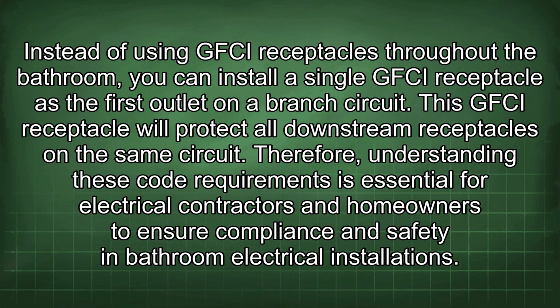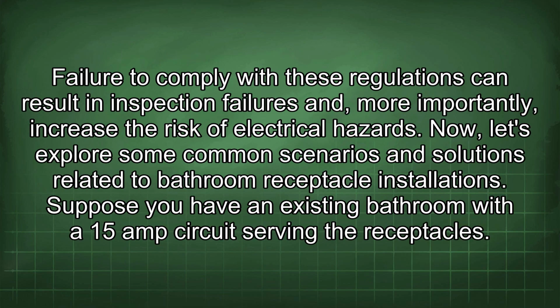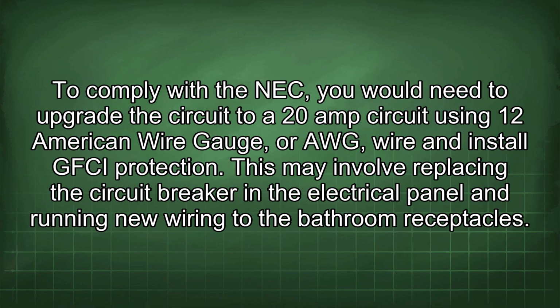Therefore, understanding these code requirements is essential for electrical contractors and homeowners to ensure compliance and safety in bathroom electrical installations. Failure to comply with these regulations can result in inspection failures and, more importantly, increase the risk of electrical hazards. Now, let's explore some common scenarios and solutions related to bathroom receptacle installations. Suppose you have an existing bathroom with a 15-amp circuit serving the receptacles. To comply with the NEC, you would need to upgrade the circuit to a 20-amp circuit using 12 American Wire Gauge (AWG) wire and install GFCI protection. This may involve replacing the circuit breaker in the electrical panel and running new wiring to the bathroom receptacles.